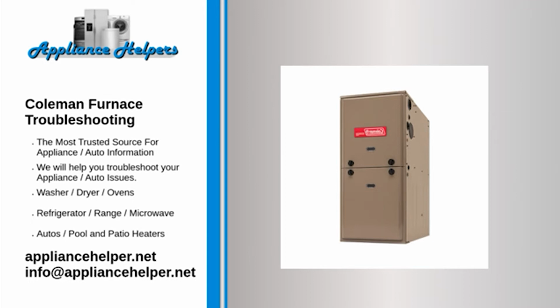The igniter has cracked or become defective. Locate the igniter within your Coleman furnace and inspect the part for cracks. If it's damaged, then you'll have to replace the part. Otherwise, test it with a multimeter for continuity to see if it's defective.